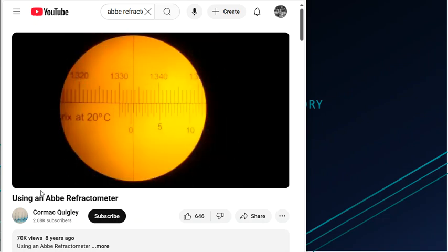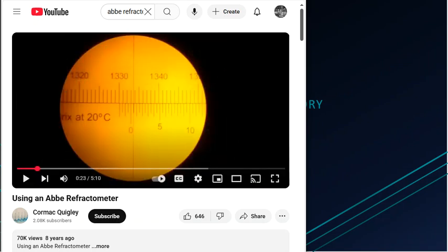If we look through the scale viewer, we can see the measurement scale. This is what you'll see when we actually write down the reading that we are getting from the manual operation. A lot of people, I think, have trouble orienting themselves on how to read this meter. This tall line here is 1.330.